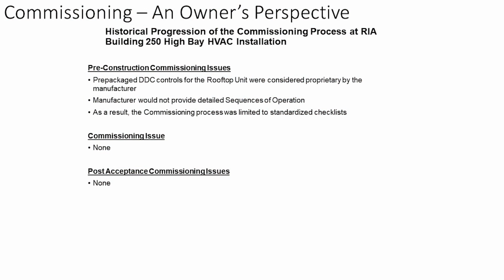prepackaged DDC controls for rooftop units. The programming was actually considered proprietary by the rooftop unit manufacturer. And the manufacturer would not provide detailed operation instructions. So how do you test something? To make the unit go into dehumidification mode, there had to be 9 different items that had to be satisfied before that unit would go into dehumidification mode. And they wouldn't even tell you what those 9 items were.